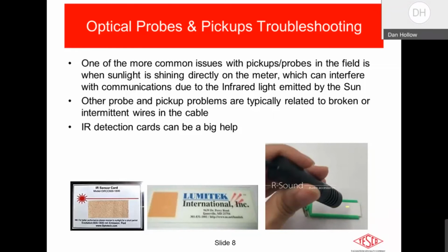Some vendors have actually taken little plastic plexiglass rods and put them in the optical port to channel that infrared light into the infrared LED and detector on the optical port. So then you have a way of channeling that infrared light so it's less likely to be disturbed by ambient light coming from the sun. But that's one of the bigger problems I've heard about, and either shading that meter or some of the precautions meter manufacturers have taken, using the plastic rod, which basically works like a fiber optic cable, channeling that infrared light, or they get the optical probe so close to the infrared LED and infrared phototransistor that the light from the sun cannot get in there and obscure the infrared photo detector, the phototransistor.